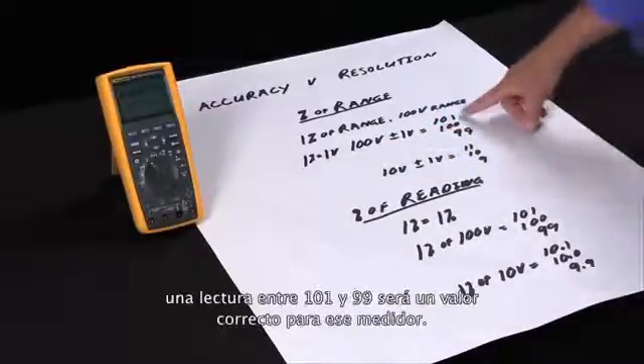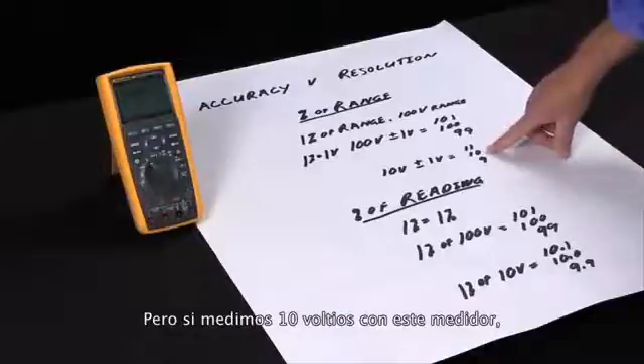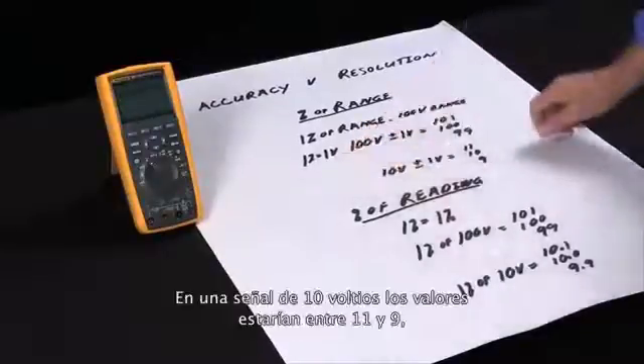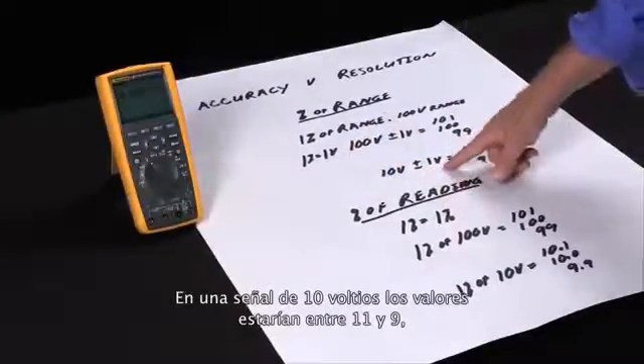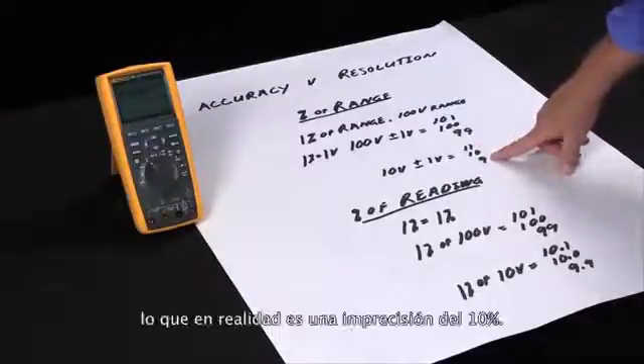So a reading between a hundred and one and ninety nine is actually a good reading on this meter. But if we're measuring ten volts on this same meter, the one percent is plus or minus one volt. On a ten volt signal, plus or minus one volt will give us between eleven and nine, which is actually an inaccuracy of ten percent.